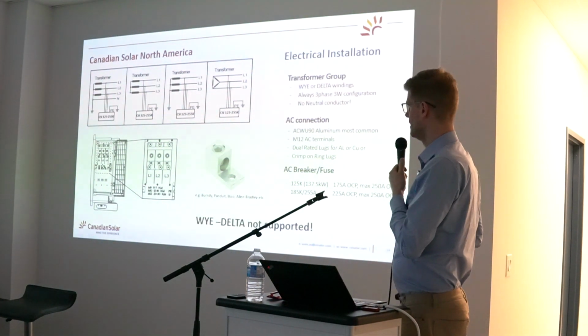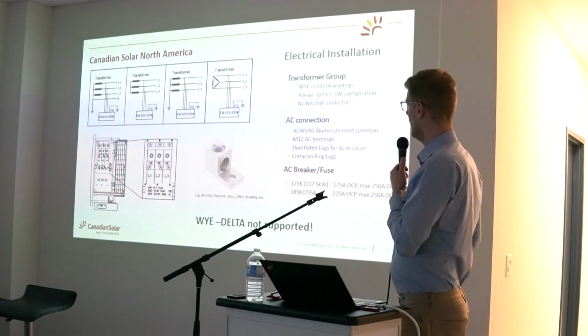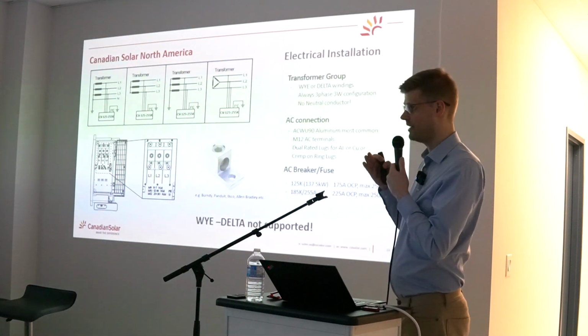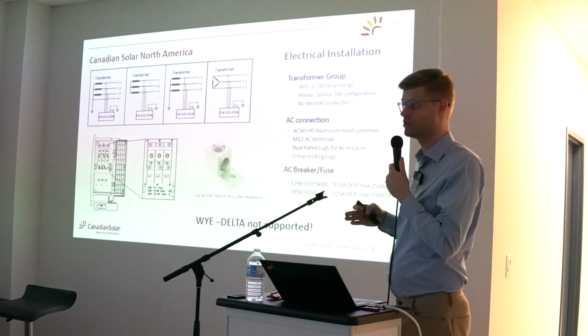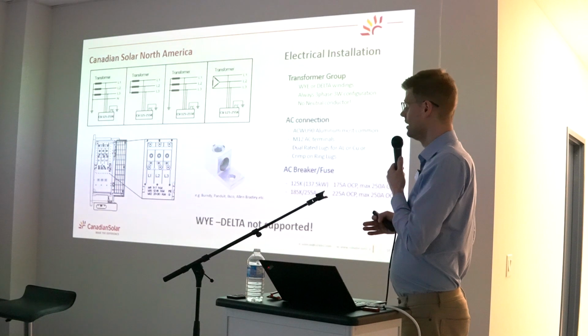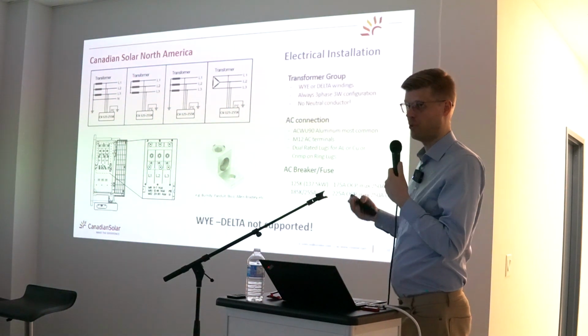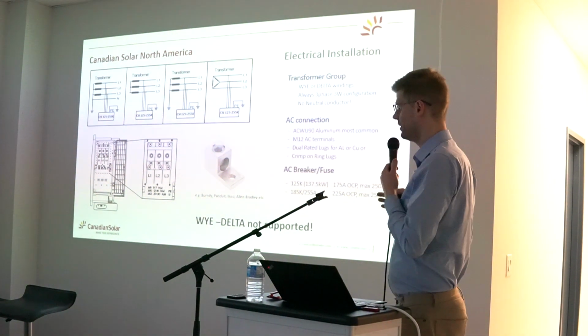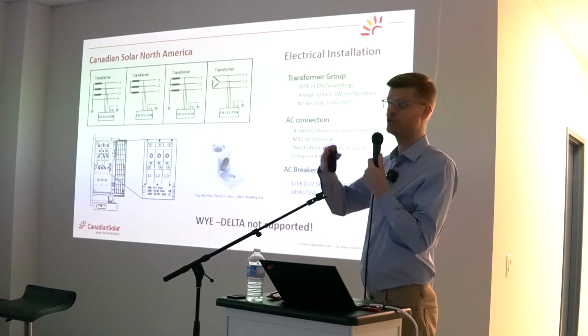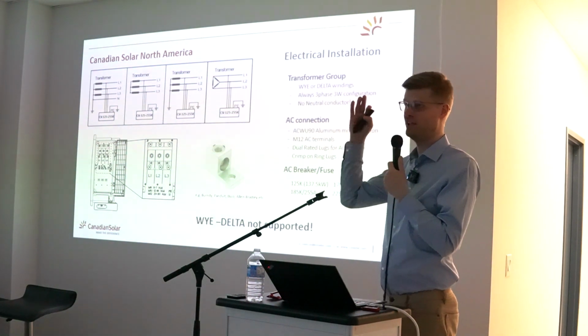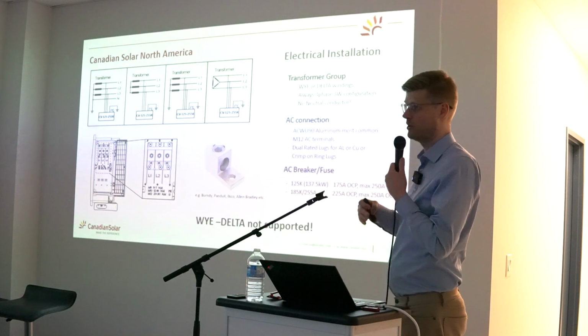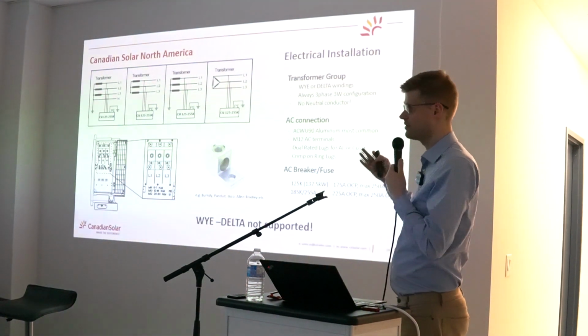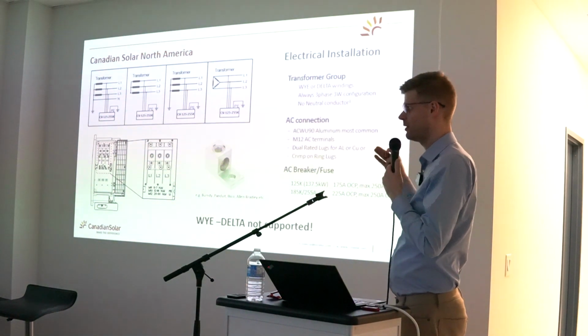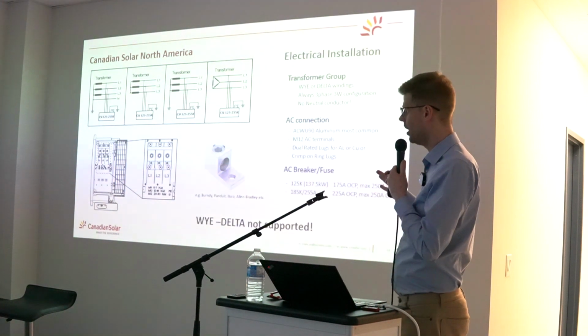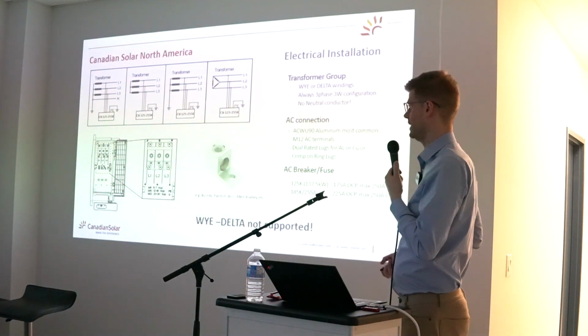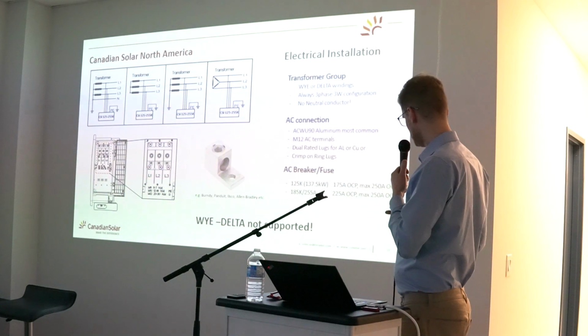is the mechanical lug. The system, as I said, 3-phase, 3-wire, does not need a neutral, will not use a neutral, and you don't have to run that fourth conductor. You can certainly run a fourth conductor if you like to. So if you want to be future compatible, let's say in 20 years there is something else, or you want to do a battery storage system with a different inverter, or a hybrid model. Not very common, but you could run one, but not connect it if you like.